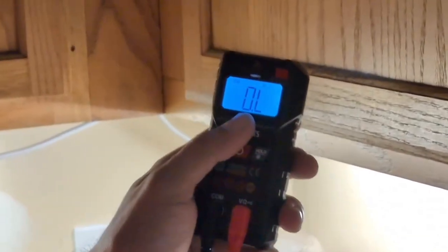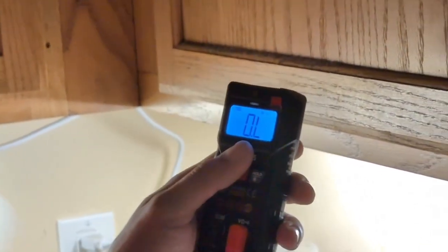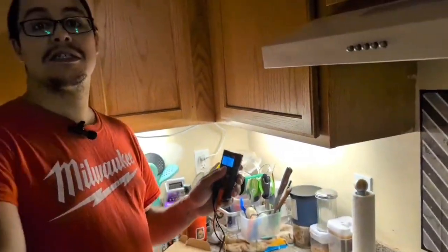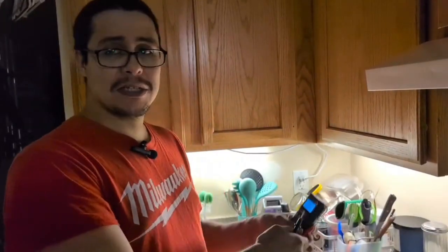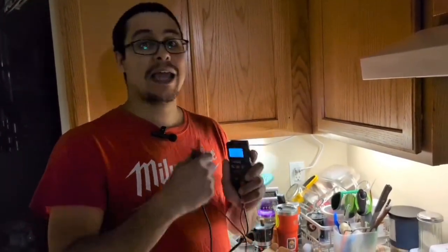And then you can do ohms. So if you want to measure, let's say, the resistance of a set of wires or copper wires going downstream, you can test the resistance, and you can also use that resistance to calculate how far the run of the wire is.